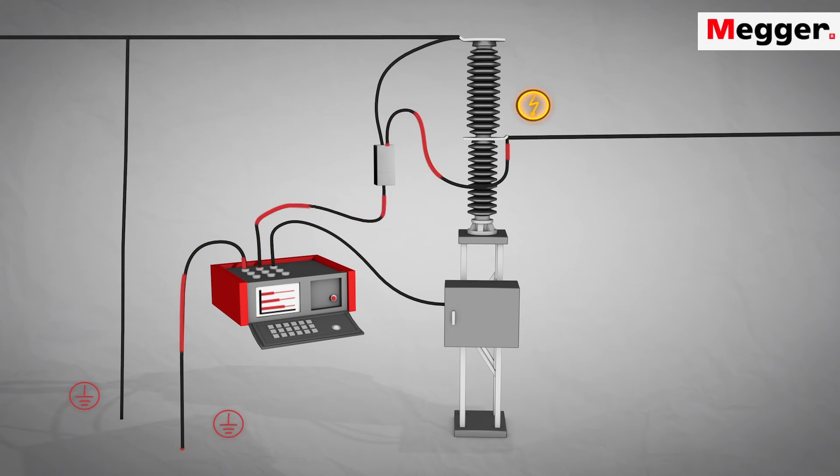When the measurements are done, the ground cable has to be attached again before the measurement cables can be removed. With Megger's dual ground method, the circuit breaker can be timed without removing the ground.